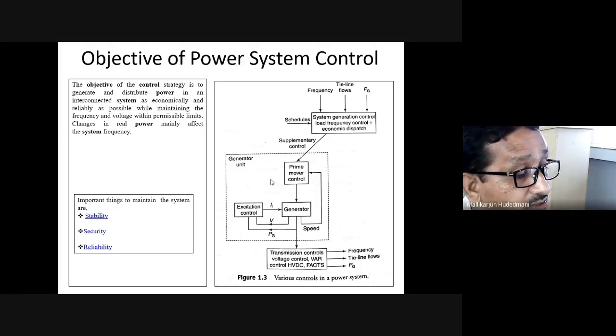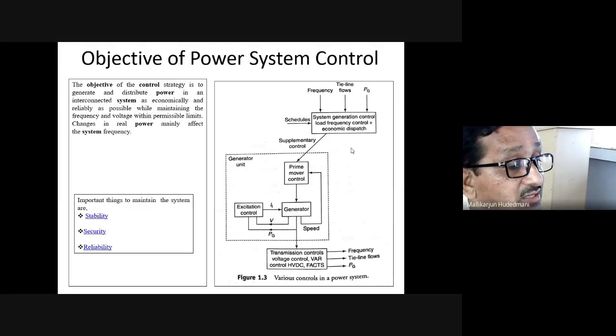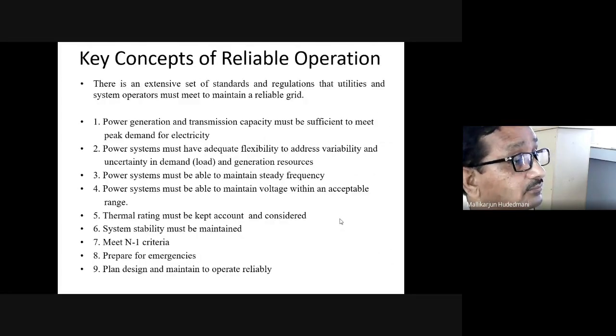This means for a simple generating unit to generate a certain megawatt and be in synchronism, it requires a command. It requires a stimulus, which has to be from the generation schedule, which has to reach this and make the prime mover appropriately controlled, and the output of which is connected to the grid, from which we measure these parameters for our monitoring. This is just a control mechanism, how it is viewed in a power system.